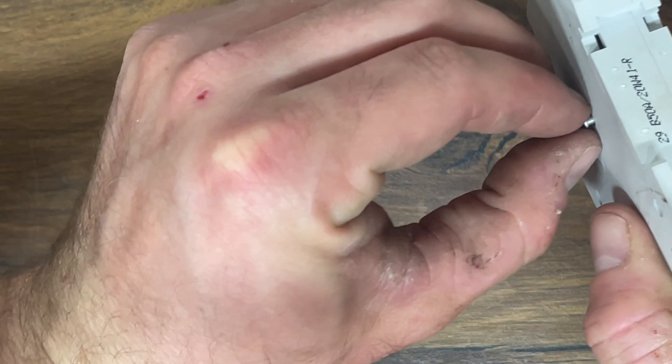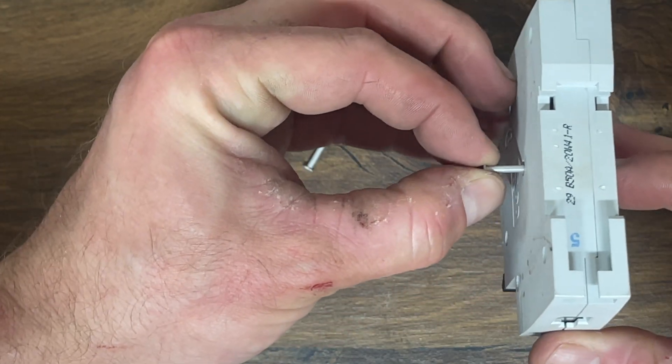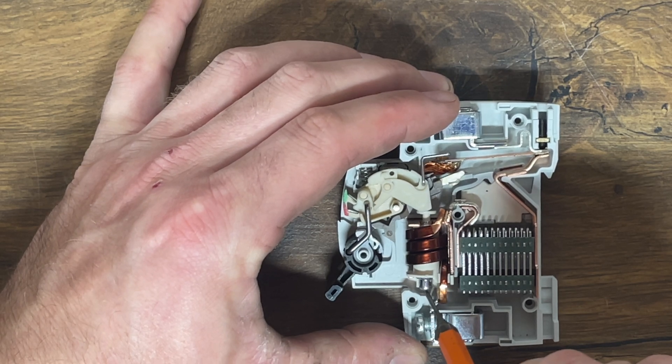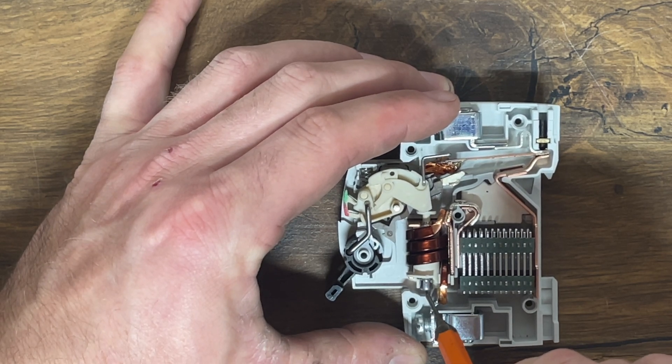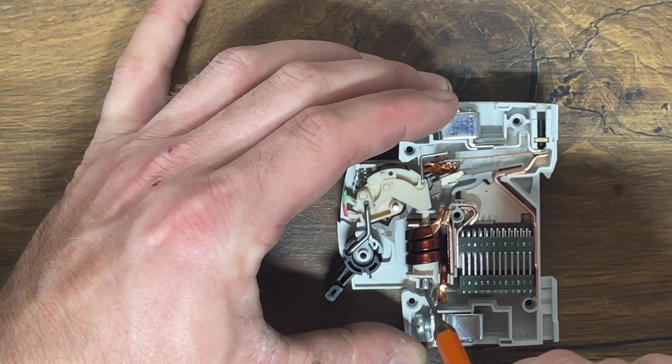Because this current is fairly high, the impulse current of the motor, it causes that MCB to trip quite fast, resulting in the little coil being the part that pushes our connection apart.